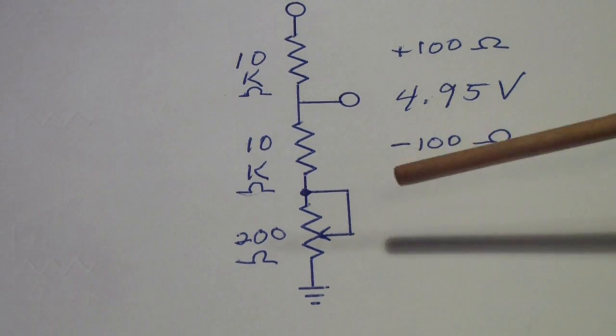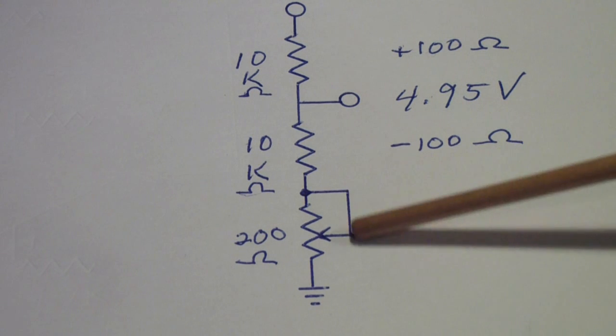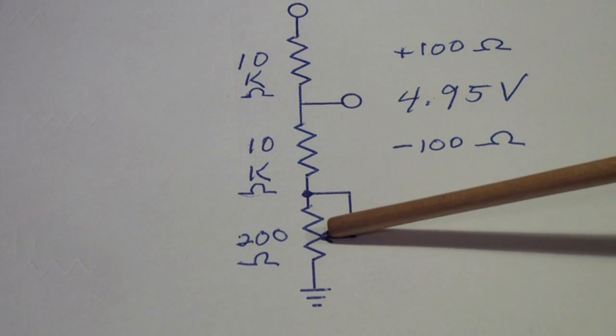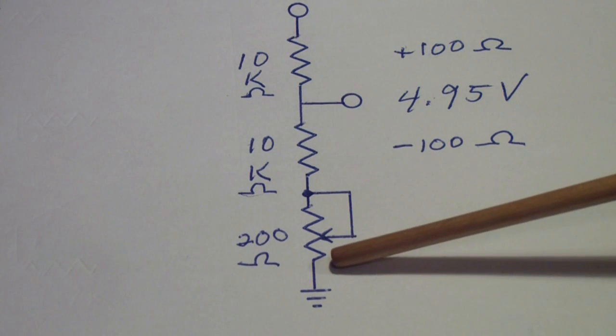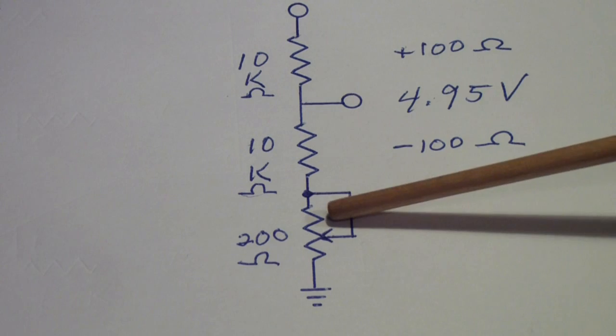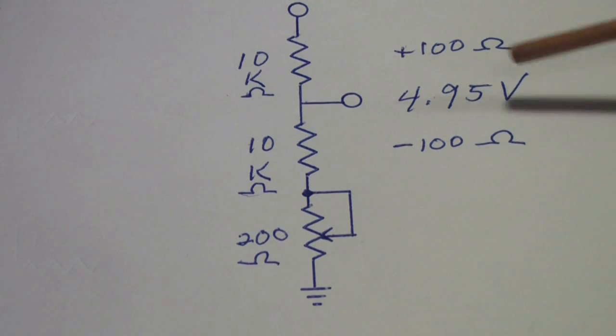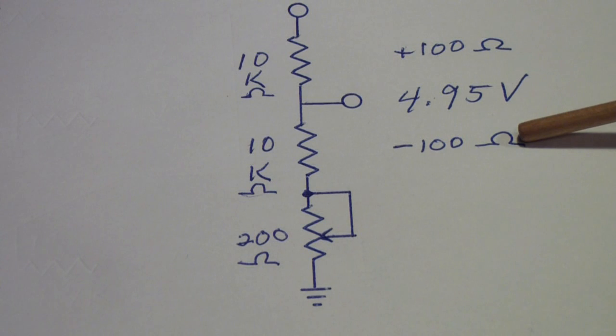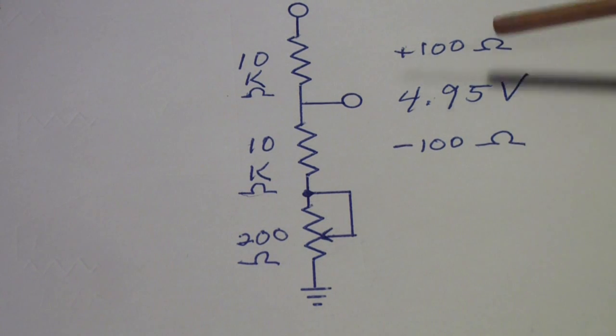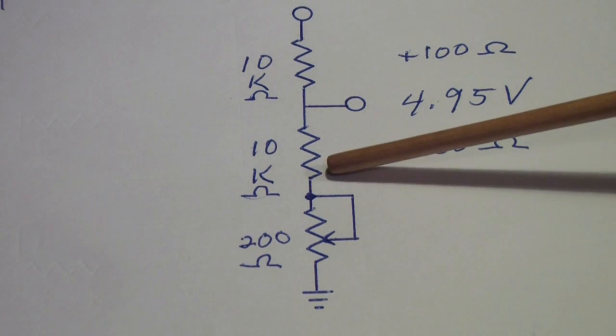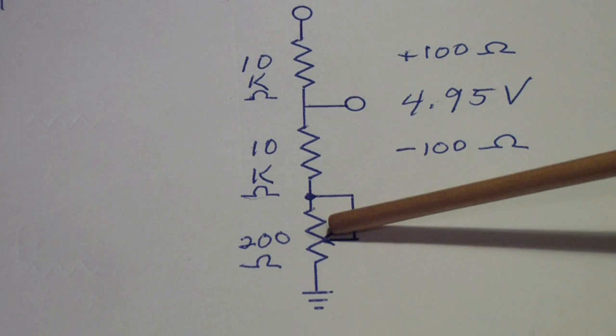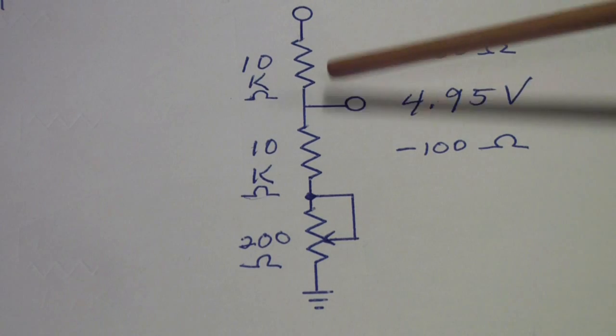So, scope manufacturers inserted a potentiometer in the circuit that would vary from zero ohms to 200 ohms. In other words, enough range to cover the worst difference between these two. There's 200 ohms difference between the highest value this one can have and the lowest value this one can have. So, if you put a 200 ohm potentiometer in here, you can basically adjust out those differences.